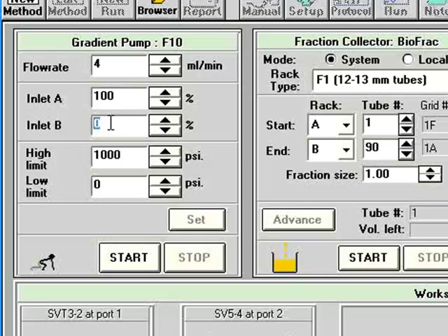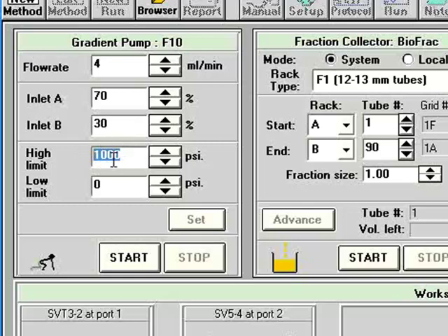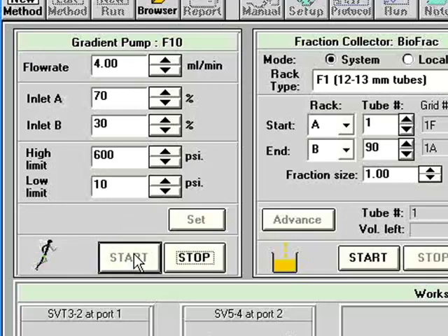If you're doing a hydrophobic interaction, obviously it's the exact opposite. But when you set a percent of one, the other goes to the opposing percent so that the two of them calculate up to 100%. Obviously you would want to set the high-pressure limit for your column, and this is where you set it here, so 600 psi, whatever the high-pressure limit is, and the low-pressure limit that you'd like to go down to for the system. Typically I set this around 10. Then you can click start, and the system will start pumping liquid according to the percent of A and B.